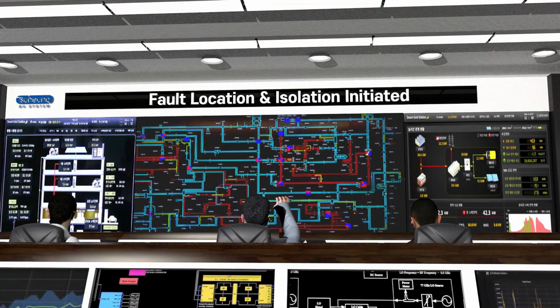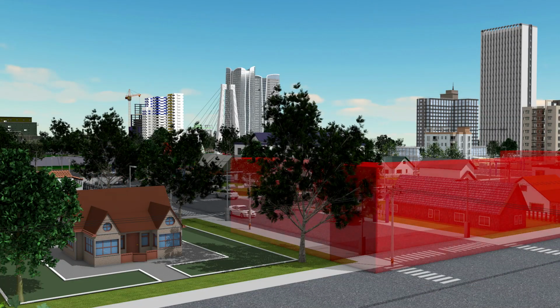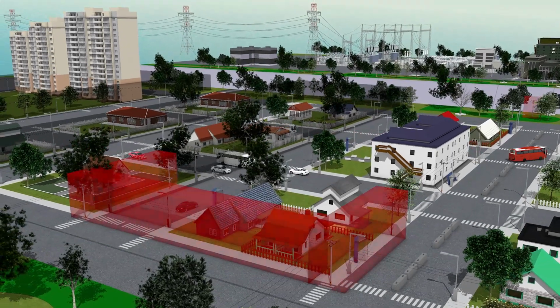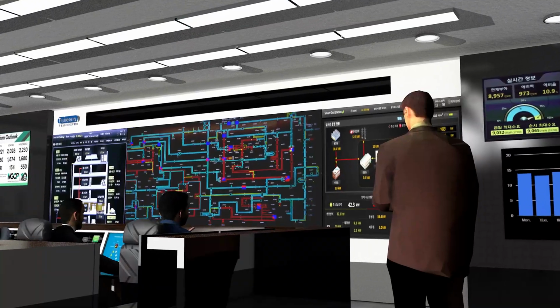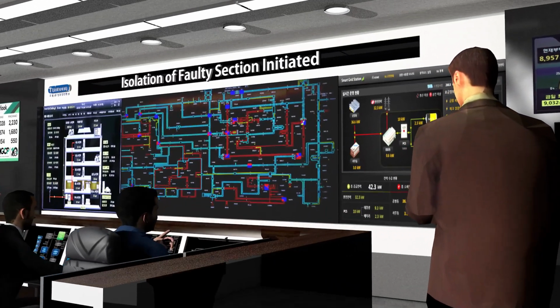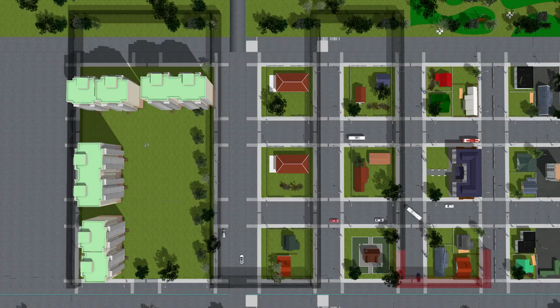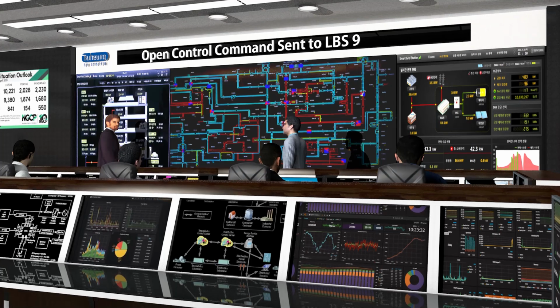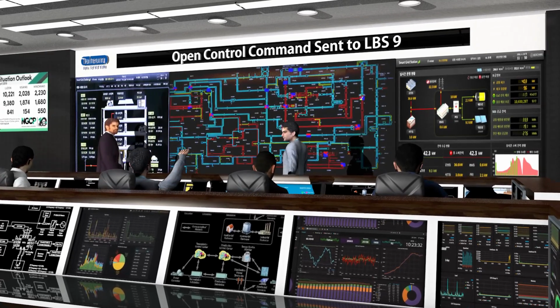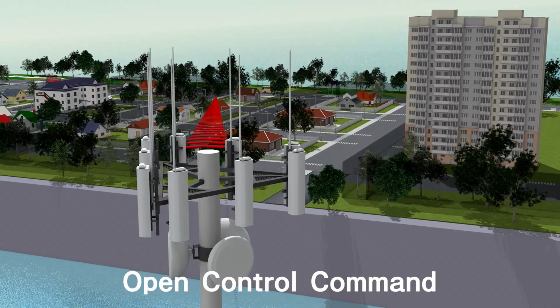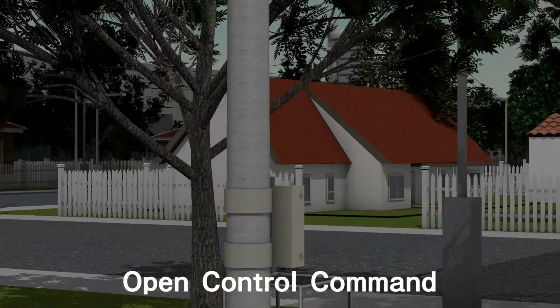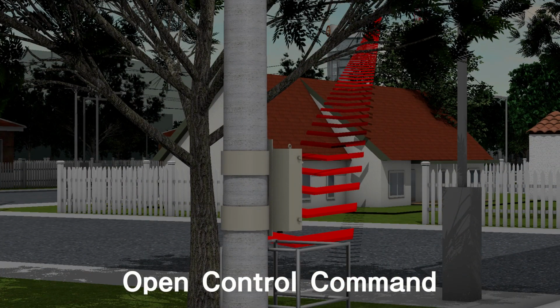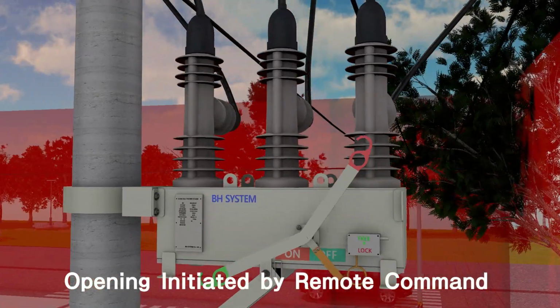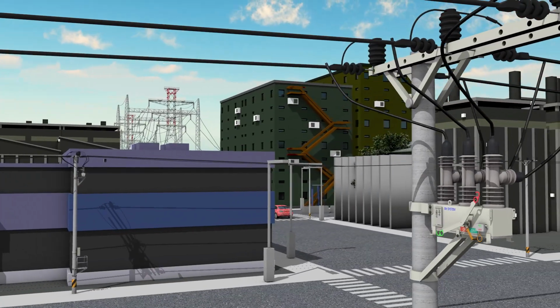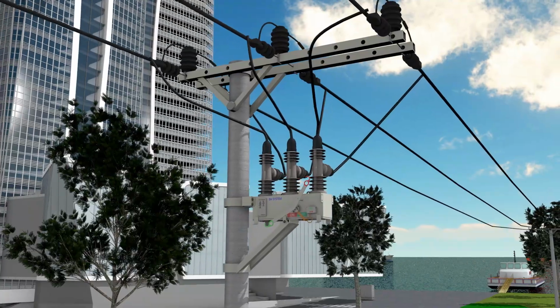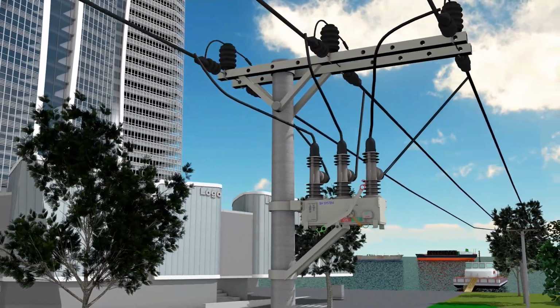The Distribution Control Center collects the status and operation histories of the reclosers and load break switches, finds the faulty section, and isolates the faulty section from the system through remote control to restore power to the healthy section of the outage. Solid dielectric pole mount load break switch has a high insulating capability and electrical durability, making the product operable in highly polluted areas such as coastal areas and factory districts.